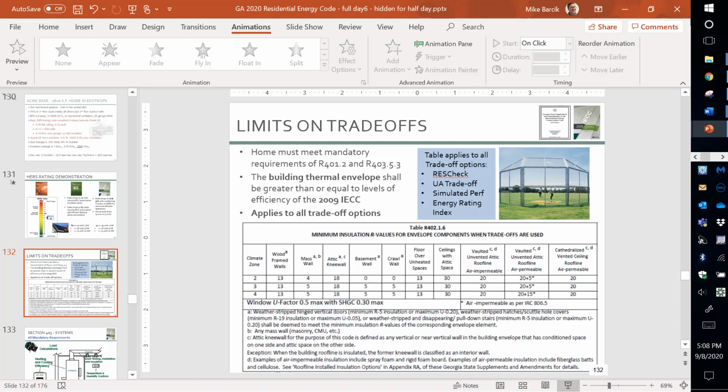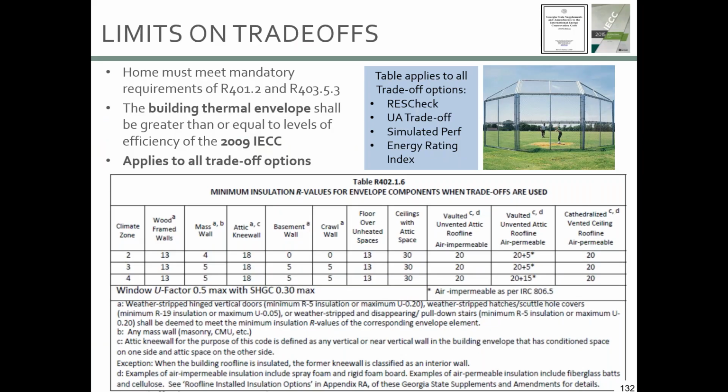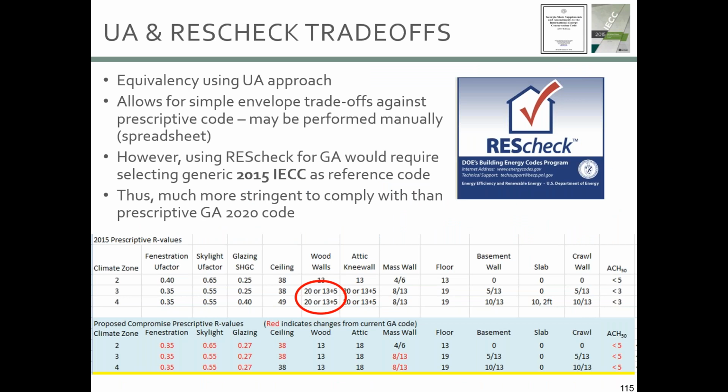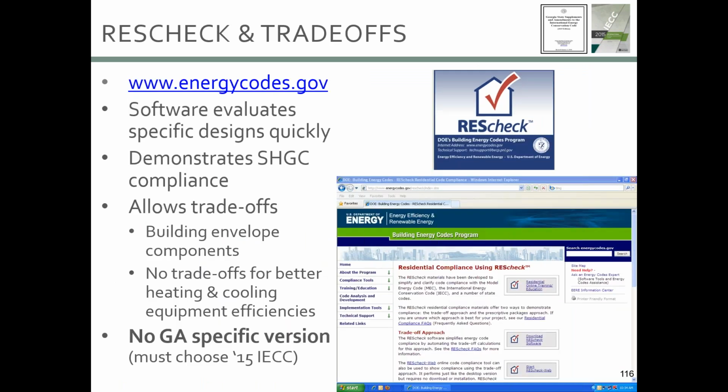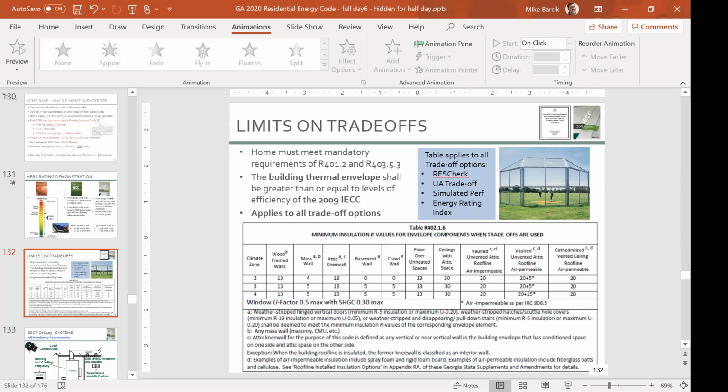in that it gives us that, I think it's this one, slide 115. Yeah, ResCheck will give us the values that we need. And here's the website to get it from. And that's another thing too, it's important to do this through ResCheck because if you just did the math and basically inverted the R value to get the U factor, it doesn't have framing factors and other things like that built in. So you really have to use ResCheck because I believe the code says it has to be compliant with the ASHRAE Fundamentals Handbook. So our tool is not necessarily that, but ResCheck certainly is.